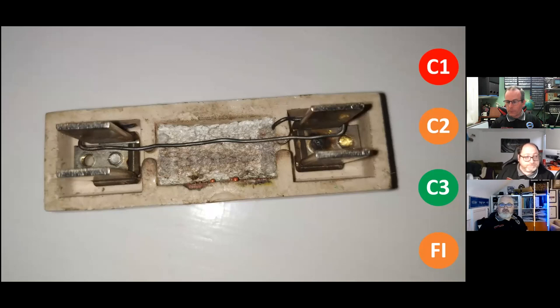Okay, so let's unveil it. What has everyone said? They're pretty much in between C2 and C1 here. Yeah, my initial thought is C2 as well. Depending on a number of external factors, use factors and the overall condition of the board I took it from, it would very probably creep up to a C1, because on an installation that age I'm sure you'd find quite a lot wrong. Yeah, there are probably many more codes to go with this board.